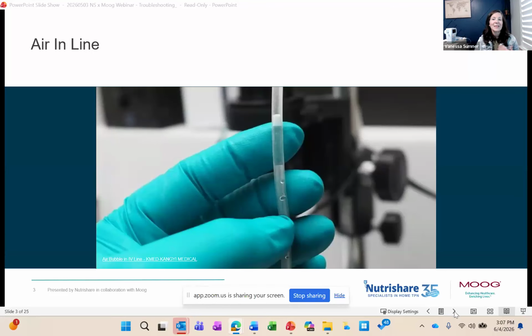Here's what we can do to decrease those air in line alarms. First, when priming your tubing, prime it slowly to help avoid turbulence. Using the prime feature on the pump will prime the line at a smooth, steady rate. You can prime the tube manually, but be careful you're not squeezing the nutrition bag and forcing that fluid down too quickly, because that will create air bubbles, which is what we're trying to decrease.